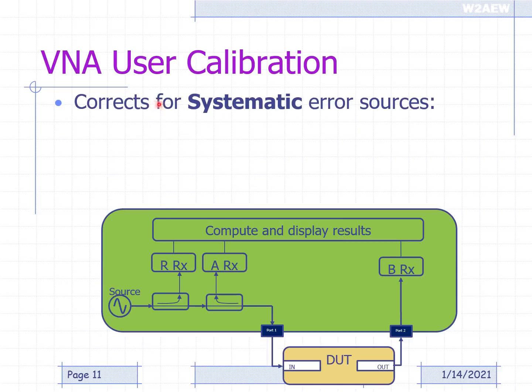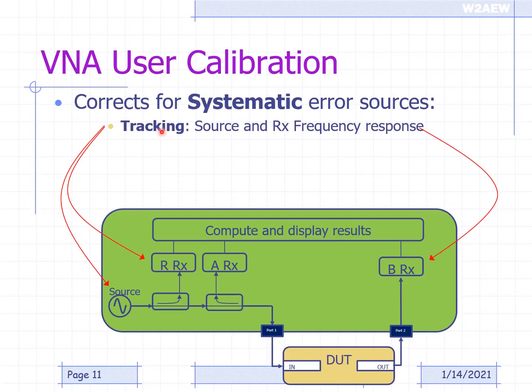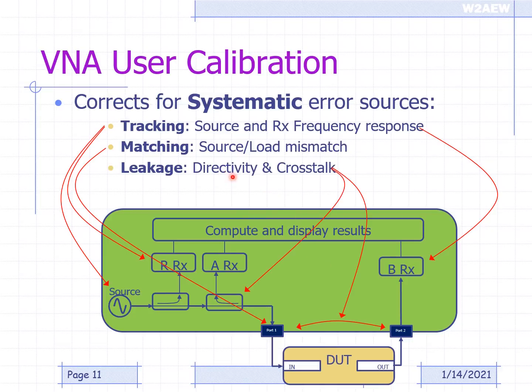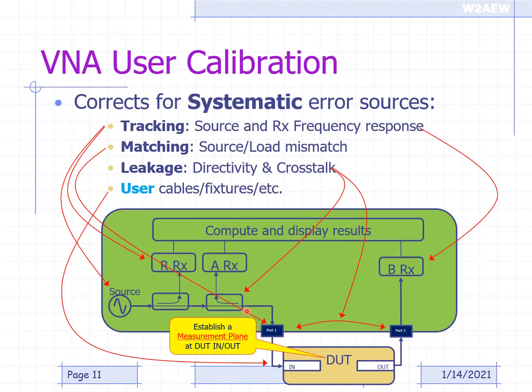So again, this user calibration corrects for these systematic errors, such as the source and receiver frequency response. Okay, the matching errors, matching at the device ports to the cables and things like that. We can remove those things as well, or even from our source to the port. So we can remove any of those mismatch errors so they don't become part of our DUT measurement. Also, the directivity of the couplers, crosstalk between the ports. We want to make sure that those errors are not part of our DUT measurement. So the user cal measures those so they can be removed from the measurement results. And then finally, we want to remove the effects of our interconnect to our DUT, so user cables and fixtures. So we establish the measurement plane at our DUT. All of these things are done through the user calibration.